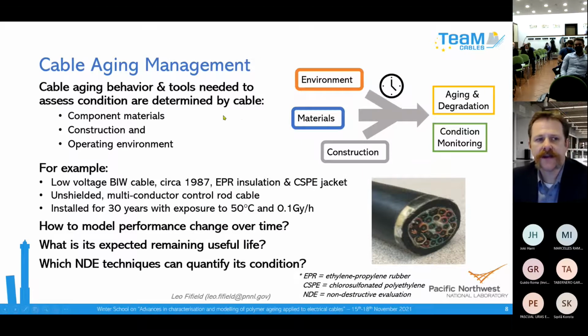To summarize cable aging management: the aging behavior and the tools to assess and quantify it depend on the components in the cable system, the construction of the cable, and the operating environment. For instance, the temperature and radiation the cable is exposed to is the environment; the materials - whether it's XLPE, EPR, PVC, or silicone; and the construction depends on whether it's shielded or not, multi-conductor, medium voltage with thick insulation, or low voltage with thinner insulation. These factors affect the degradation and the ways you can assess it.